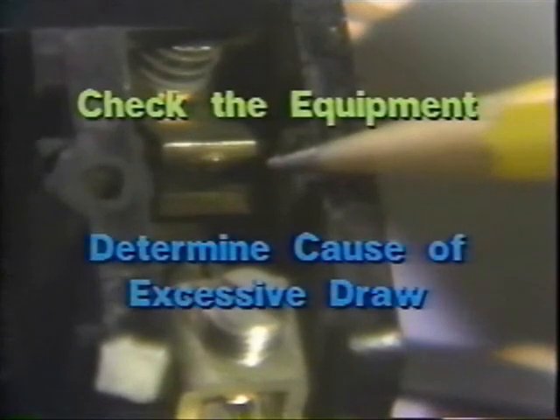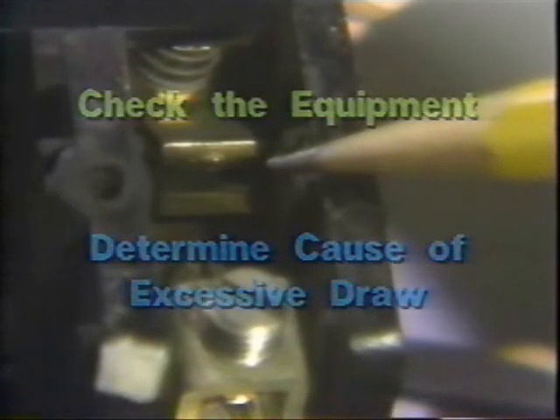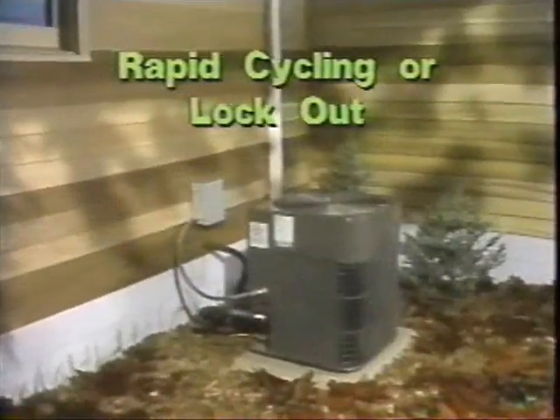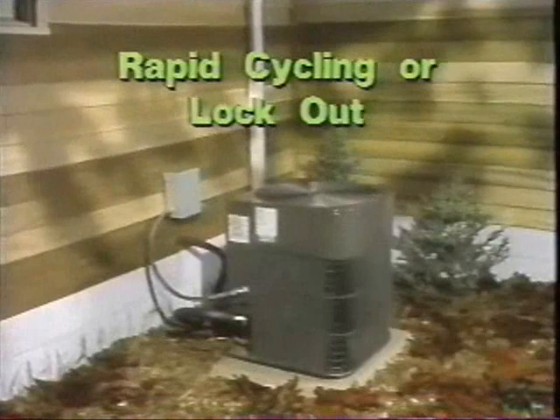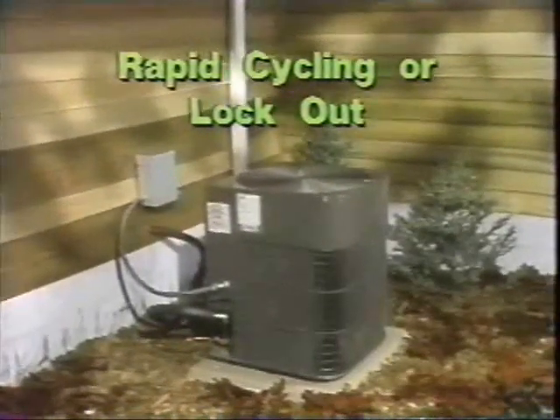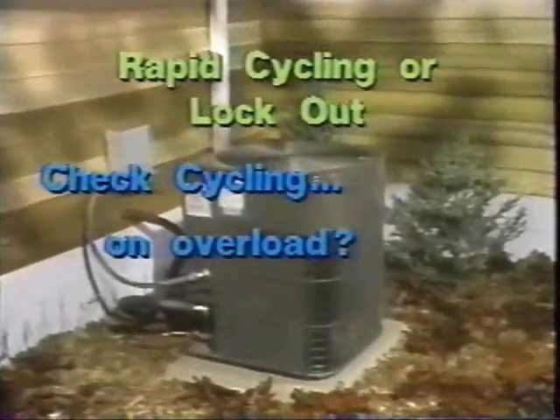It is also possible for the contacts to weld together as a result of excessive current draw. Although you must replace the contacts, also check the equipment on the line to determine the causes of the excessive current draw. If the contactor is too small to handle the load, the result is the same. If the system starts but rapidly cycles or locks out, check to see whether the compressor is cycling on overload, high pressure, or low pressure.